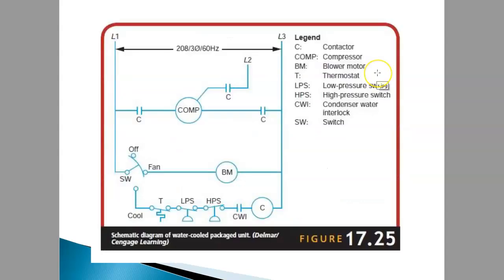Let us see the diagram. Okay, this is a schematic diagram of water cool package unit. So, for example, here we have a contactor, legend of C, compressor, BM blower motor, T here is thermostat, LPS low pressure switch, high pressure switch, CWI condenser water interlock, and last one is switch. So this is switch, on and off. This is contactor. It has 1, 2 and 3 contactor.